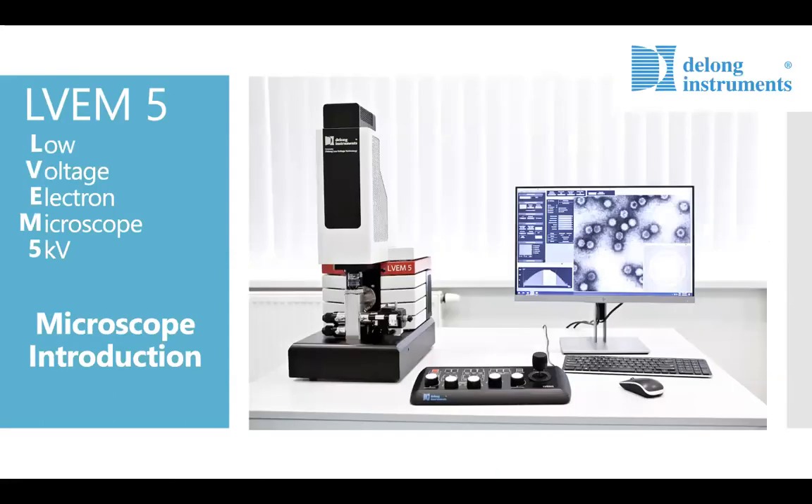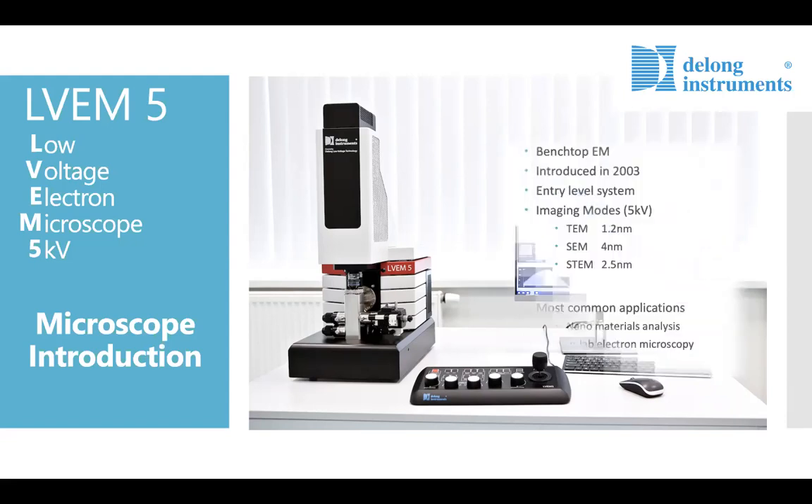There are two commercially available low voltage electron microscopes, both made by DeLong Instruments — the only manufacturer in the world of LVEM technology. The LVEM 5 was commercially introduced in 2003 as a benchtop system, considered the entry-level instrument. The '5' represents the 5 kV accelerating voltage, which provides resolutions of 1.2 nanometers in TEM mode, about 4 nanometers in SEM mode, and about 2.5 nanometers in STEM mode. The most common applications are nanomaterials analysis and in-lab electron microscopy.